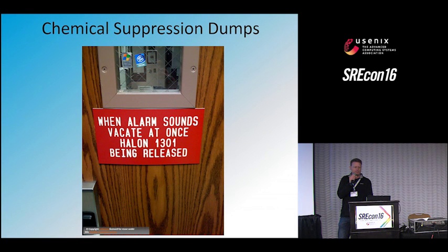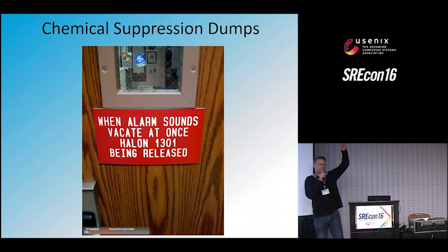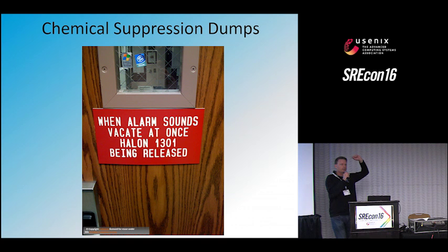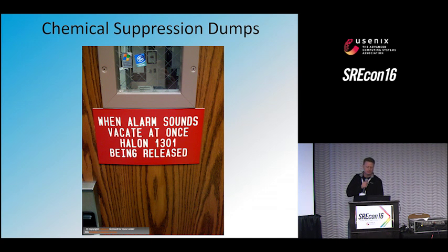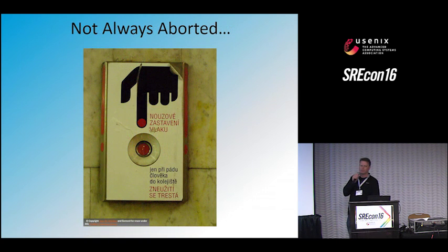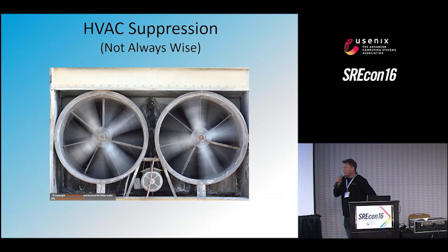A couple of real-life stories. Fake fires. This is a previous company I was working at. Somebody was soldering in the corner of the data center. A little whiff of smoke comes off. When that red light starts blaring up there, it means you're about to trigger a fire suppression system. That means you either need to hit the big red abort button or get out of the data center. Our guys didn't do either. Fortunately, we don't use Halon anymore, so they survived.